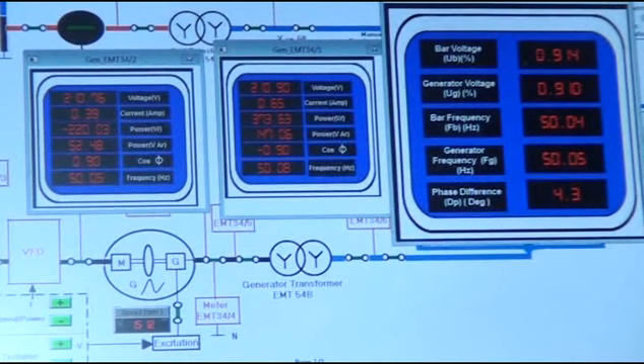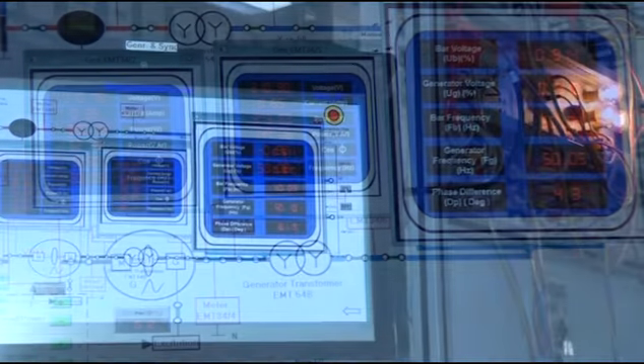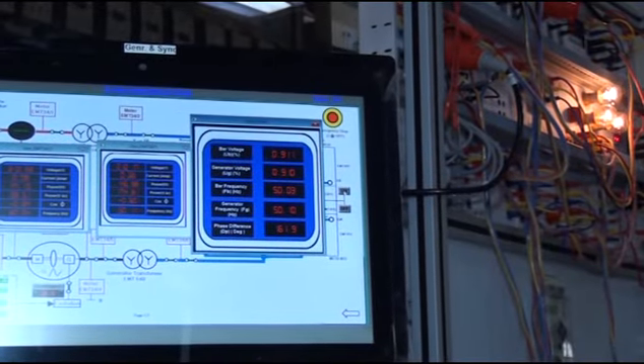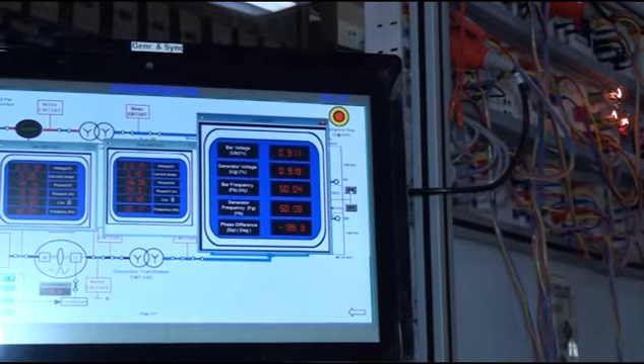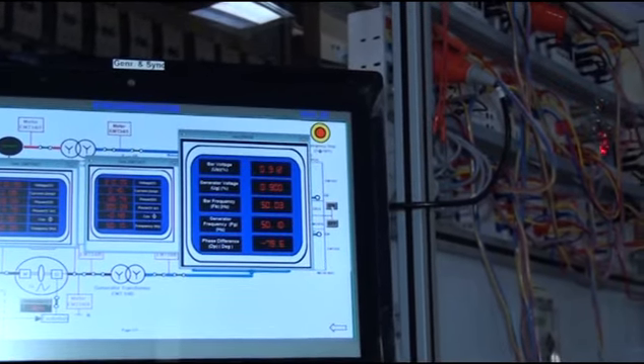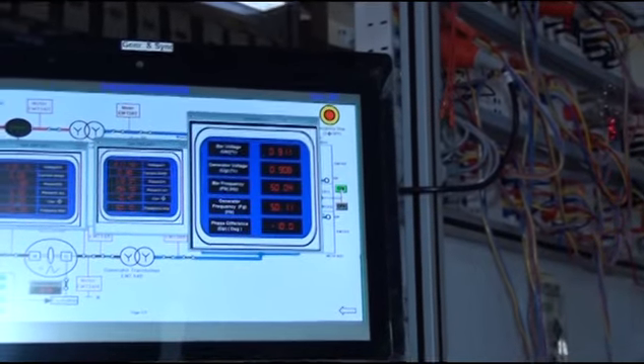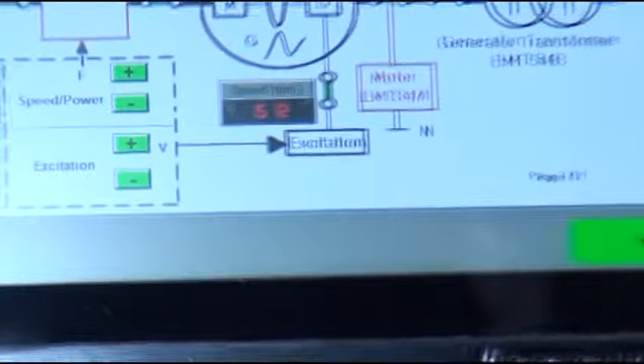This is the synchronization relay screen, to observe generator voltages and frequency and grid voltages and frequency. Both are the same. Now observe the three bulbs at one moment. The phase difference between grid and generator is 0. At that moment, press the synchronization switch. That means when the bulbs are in off position, we press the synchronization switch, since it is the dark lamp method. Now we observe the synchronization done message on the touch panel.